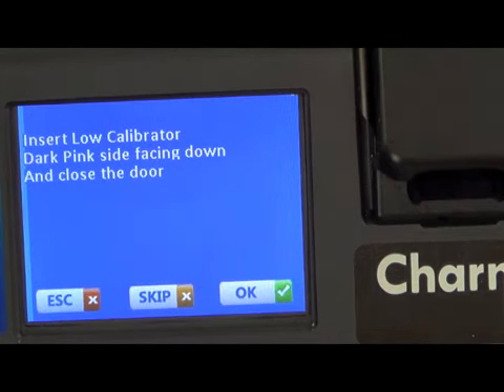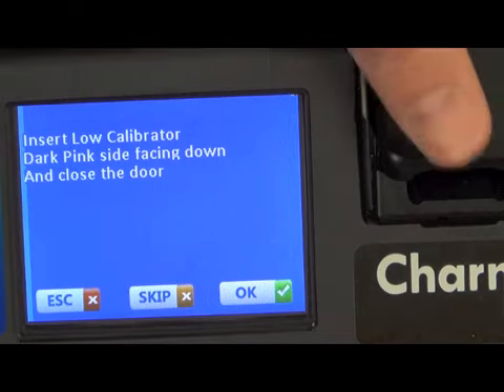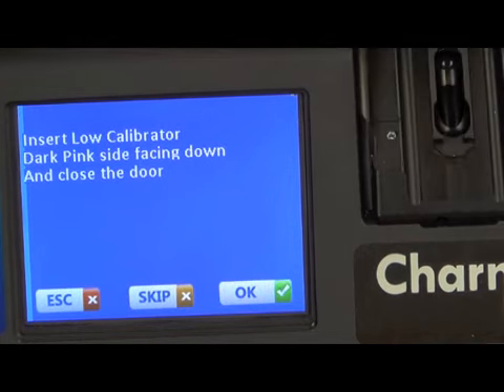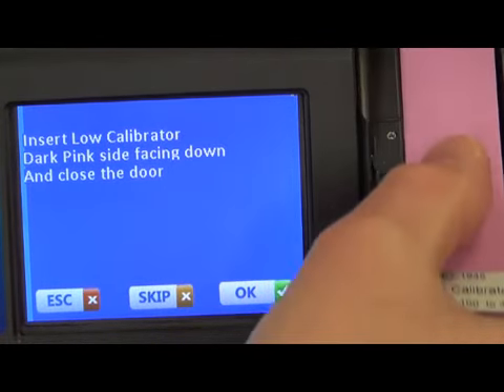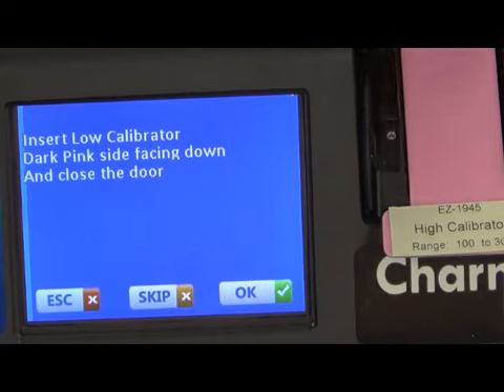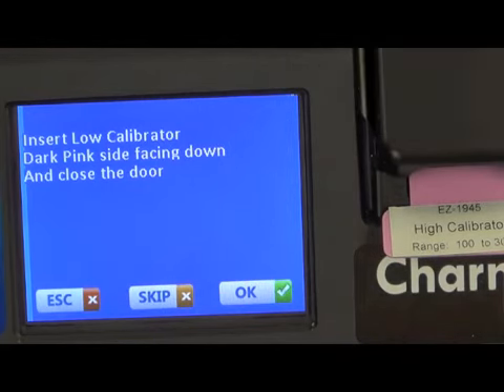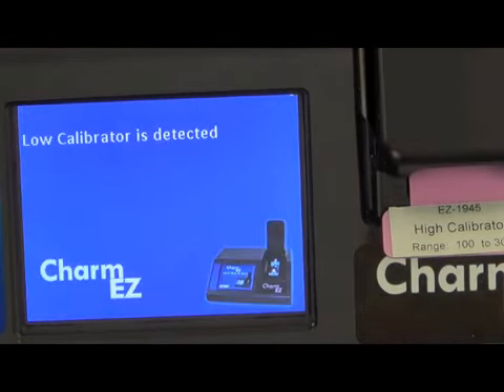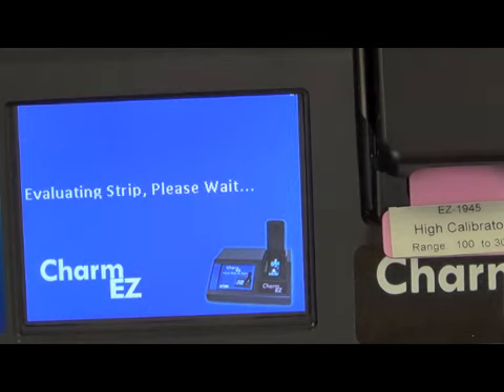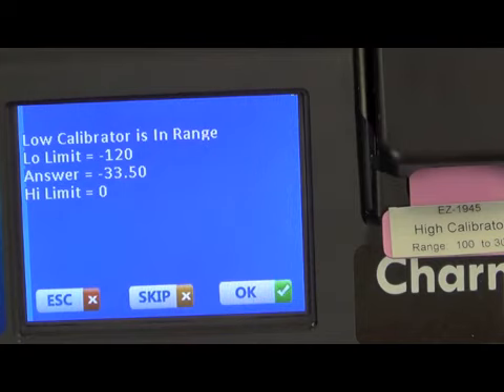Follow the prompts on the screen. The first selection is where it's going to say to insert the low calibrator. This means insert the dark side of the calibration strip facing down. Close the lid to the EasyReader and press OK. If the calibration strip is in range, you will get a message with the appropriate value compared to the upper and the lower limits, and a reading where it says low calibrator is in range.